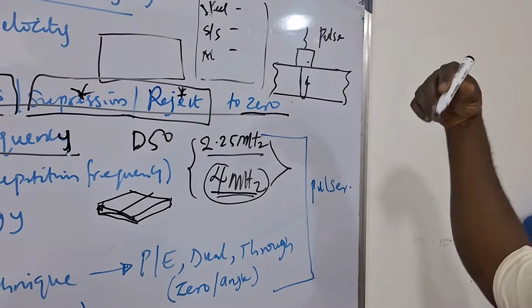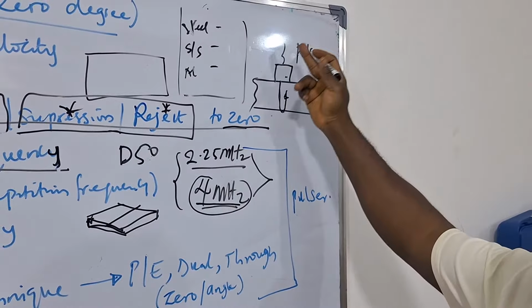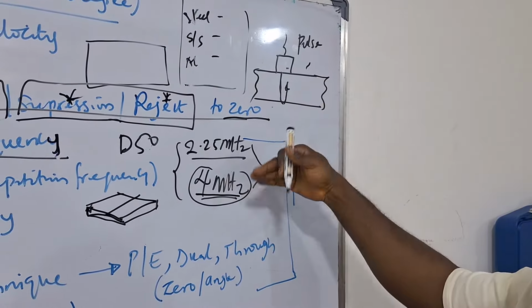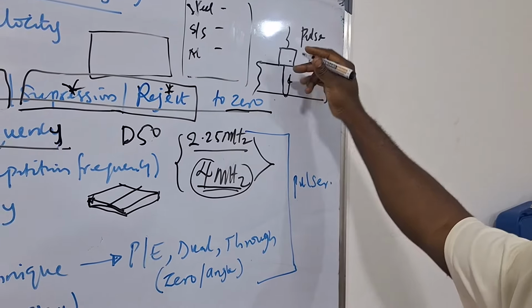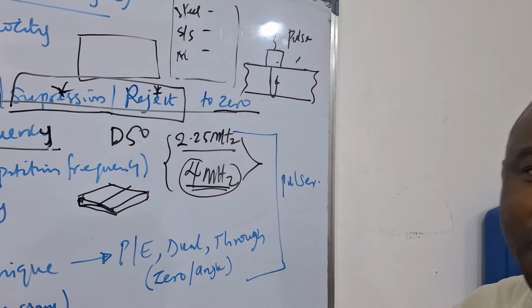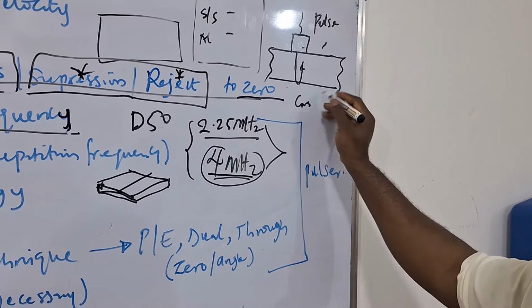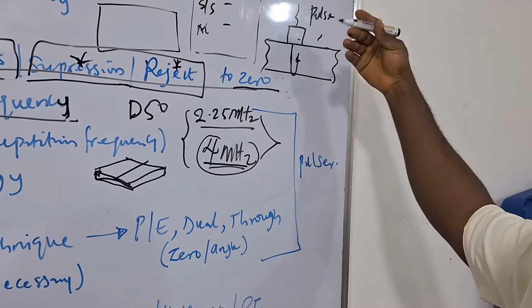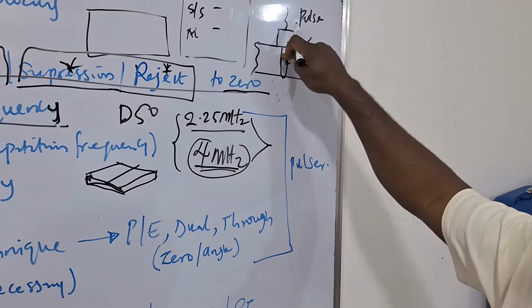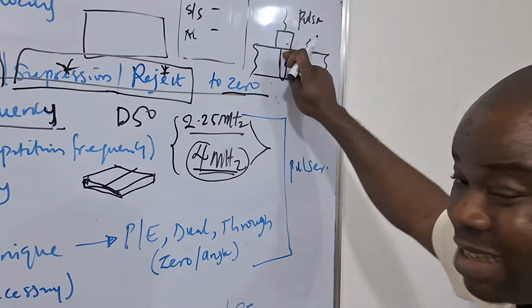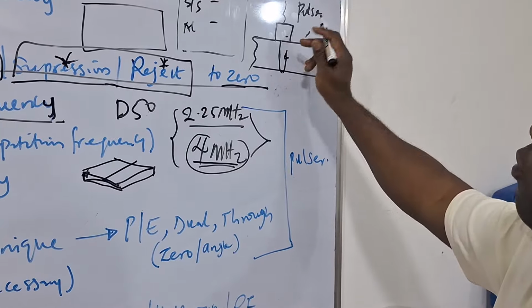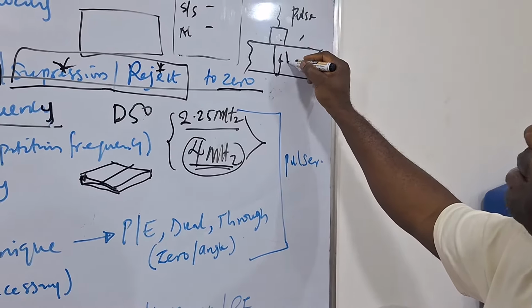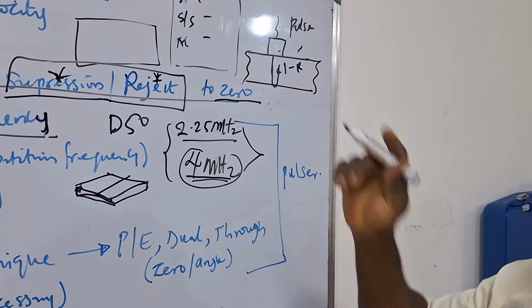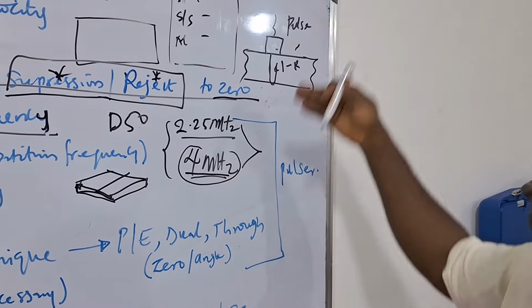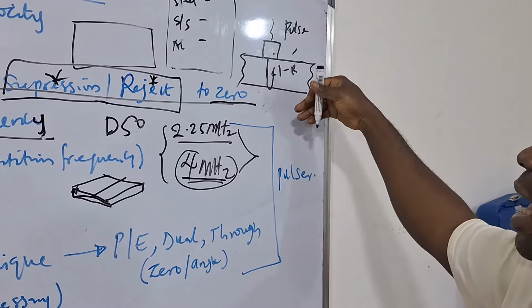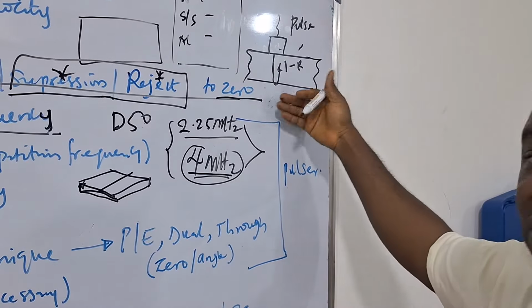Which means if you have a very high PRF, as you are sending one, the next one follows immediately. The next one follows immediately. If you have a lower PRF, it means when you send in one pulse, you wait a little time, then you send in another pulse. If you have a very, very high PRF, it's going to cause what we call crosstalk, or rather not crosstalk, noise. It will cause noise because the returning echo will start interfering with the ultrasound that you are sending in, the one that you are transmitting. So if you have too high a PRF, the incident signal will be interacting with the reflected signal, thereby leading to a form of noise in your unit. It may not be something that will be obvious to some people, but if it gets very high, it will cause some distortion in your signal and even affect your results.